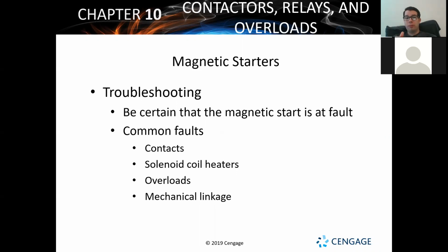So troubleshooting a magnetic starter, basically you're going to be making sure you're looking at contacts, coil, overloads, and mechanical linkage. So the same parts we've already looked at for contactors and for relays, we're also going to be looking at for magnetic starters. But with a magnetic starter, remember, it's also going to be having an overload device. That overload device is something else you have to troubleshoot.